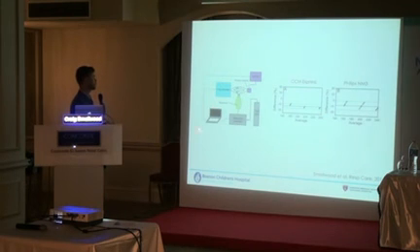We manufactured a system to validate it. So we're setting a specific amount of energy that we want to estimate, and then measuring how much came out of the ventilator itself, or the device to measure it. You can see that both of them underestimated by about 10%, but 10% in ventilation and in healthcare I think is not too bad.